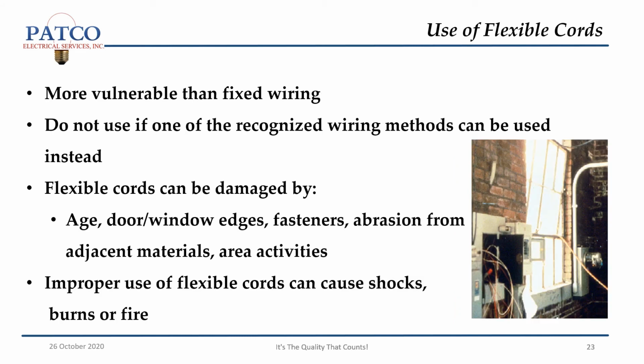Use of flexible cords. They are more vulnerable than fixed wiring. Do not use them if one of the recognized wiring methods can be used instead. Flexible cords can be damaged by age, door or window edges, fasteners, abrasion from adjacent materials, and area activities. Improper use of flexible cords can cause shock, burns, or fire.